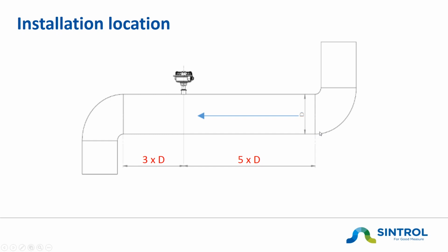Absolutely never install it straight into a bend or right after. The conditions there are so turbulent and foremost they are varying with the air and the flow speed. Now, if you don't have such a long piece of ductwork, make sure that you keep the relation 5/8 to 3/8, meaning you should be always a little bit more away upstream from the last bend than you are downstream.